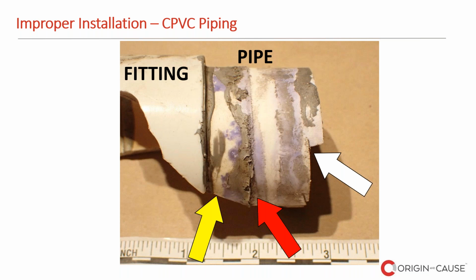And obviously, there was another issue here, which is that the pressure was on the high end of the specification. So even if they had done a better job at cutting the pipe, it is still possible that they didn't wait long enough for the joint or the cement to cure, and in that way, just separated. So a number of things to consider when it comes to installation of CPVC systems, and why they separate. But again, going back to the basics is always important. So documenting, interviewing, and securing the evidence.